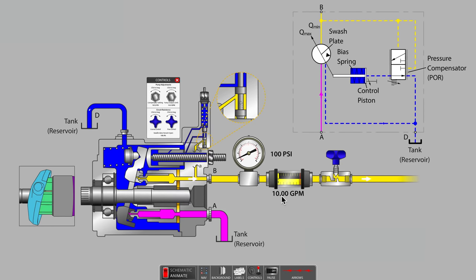As you can see, when there is an easy flow path for the pump's displacement, changing the setting of the pressure compensator spring has no impact at all on system pressure. In a real-world hydraulic system, the maximum system pressure limit would now be unknown; this could easily become a dangerous situation.